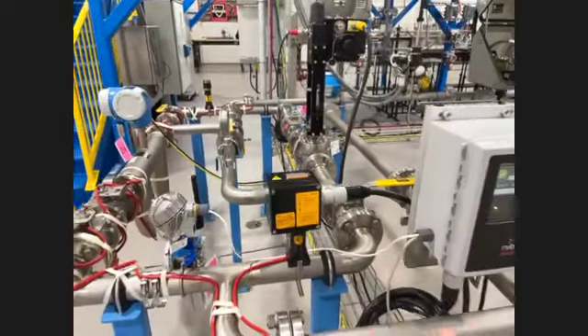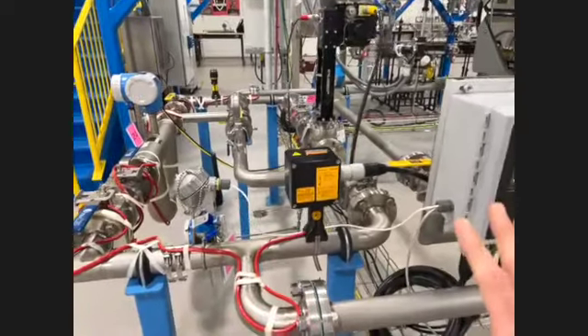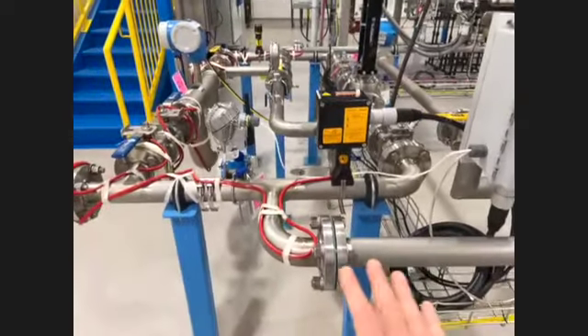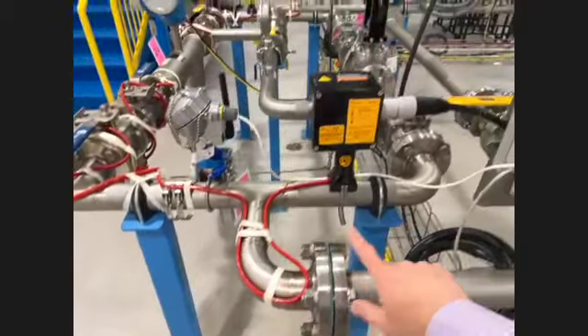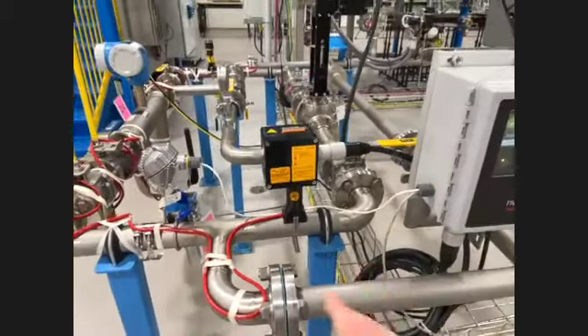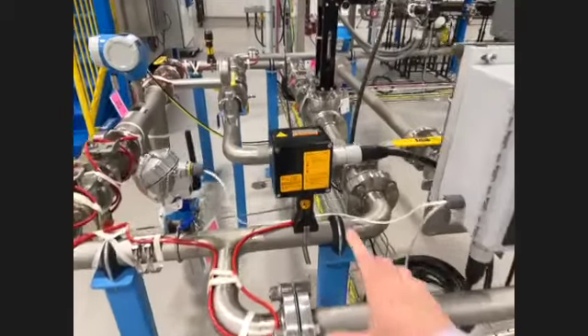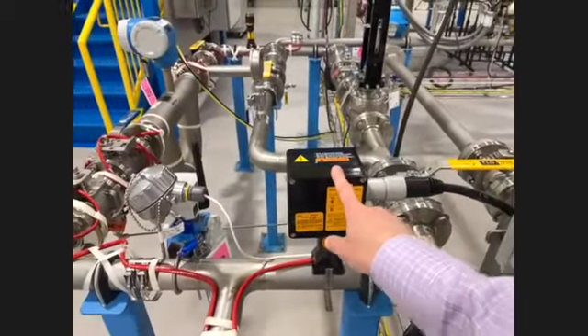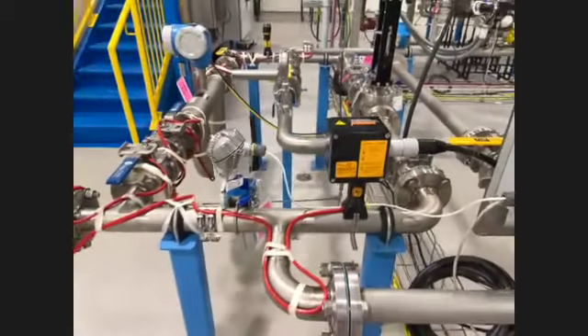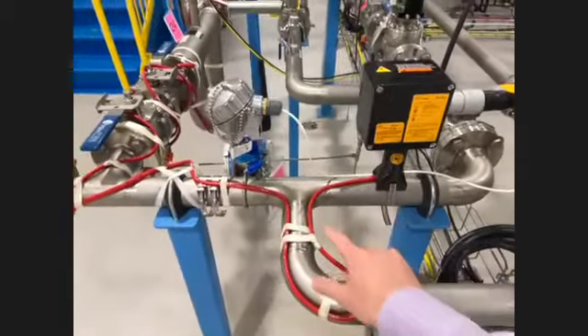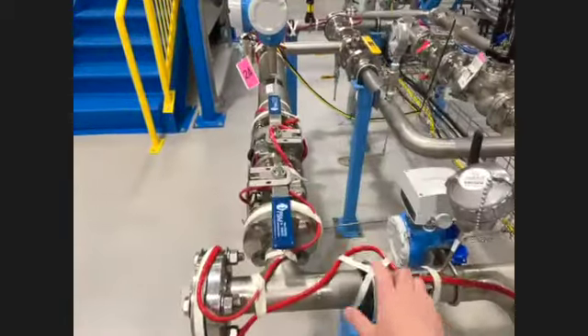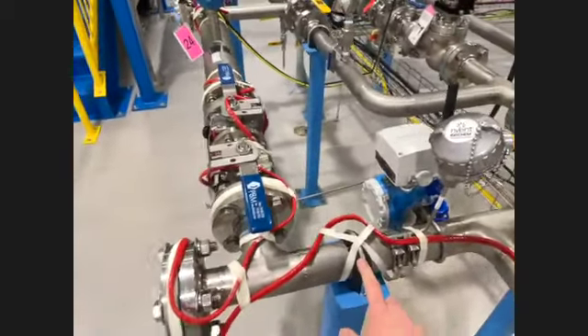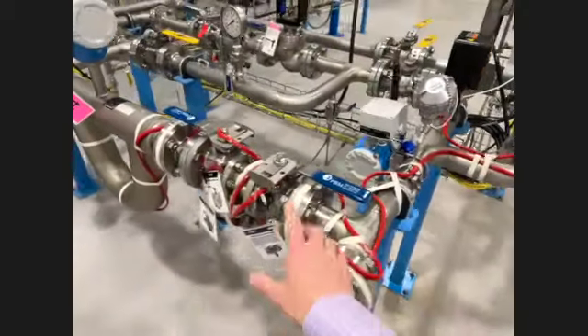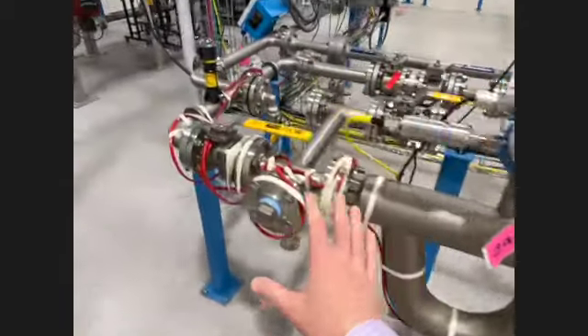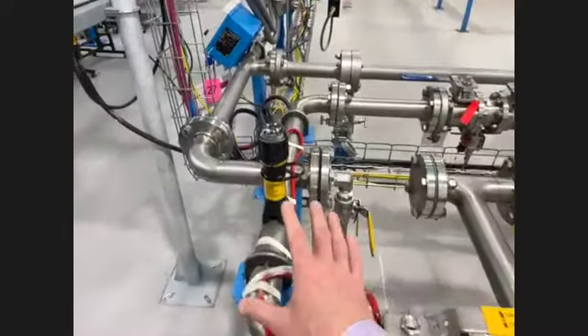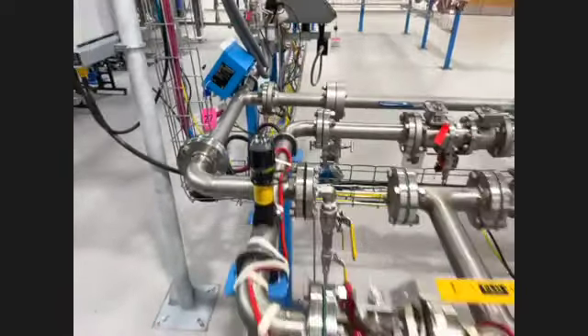This power connection kit is your transition from building wire to heat tracing wire. A common misconception is that the heat tracing cable that you see here needs to be run back and terminated inside the controller, and that's not the case. The heating cable always stays on the pipe, and this typical component is where you transition again from building wire to heating cable. So you can see here our heating cable is coming out. It's wrapping around. A little bit of an extra loop here because there's a pipe support, and you also have a flange, valves, Coriolis meter, all the way down here, wrapping more valves and supports. And then this is your end seal where you cap off the end of that heating conductor.